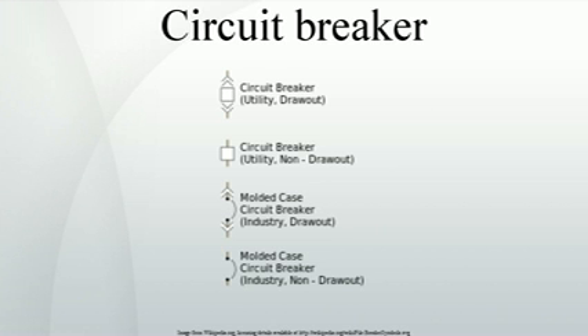Types of circuit breakers. Many different classifications of circuit breakers can be made, based on their features such as voltage class, construction type, interrupting type, and structural features. Low-voltage circuit breakers. Low voltage, less than 1000 VAC, types are common in domestic, commercial and industrial application, and include MCB, miniature circuit breaker, rated current not more than 100A, trip characteristics normally not adjustable. Thermal or thermal magnetic operation.